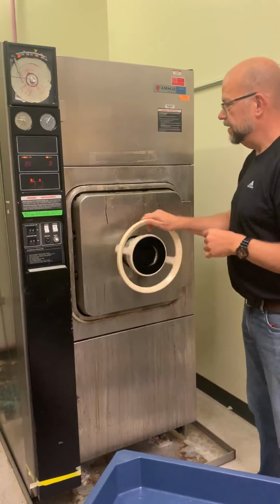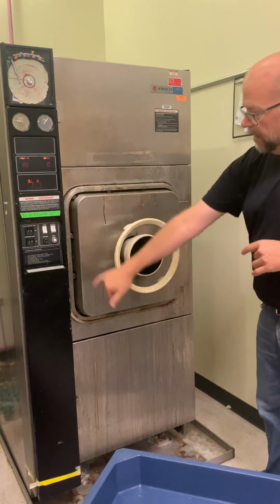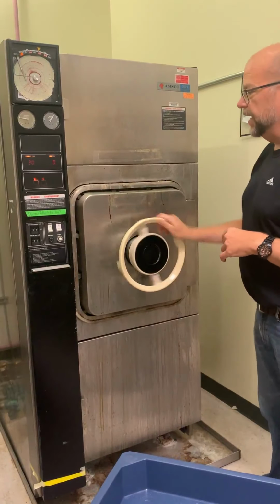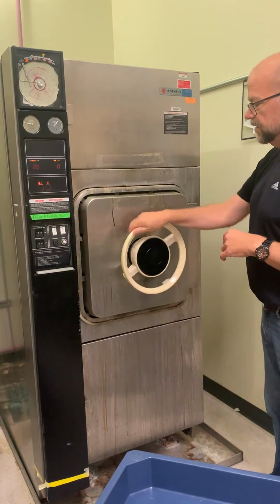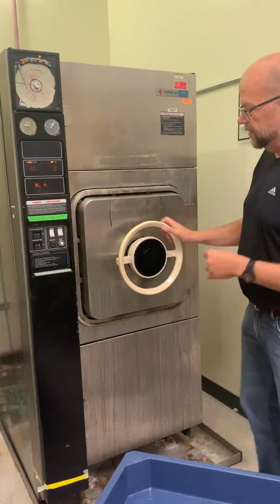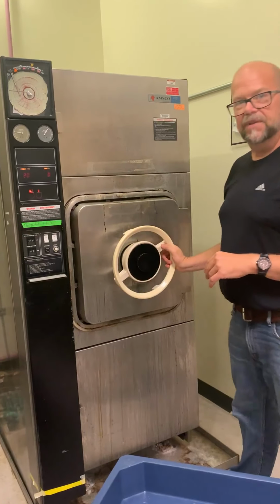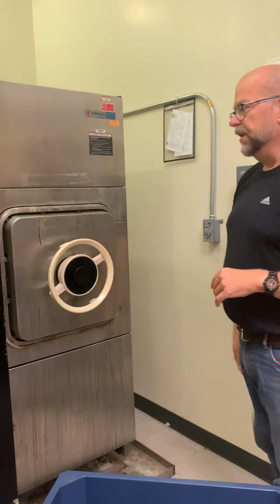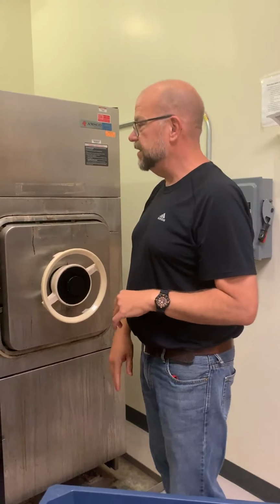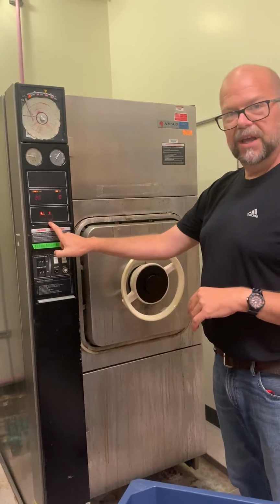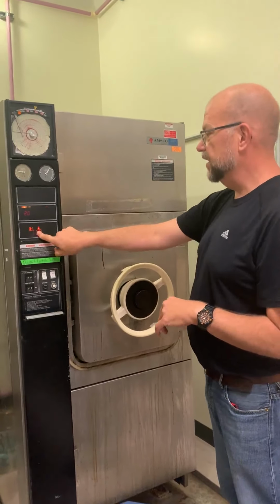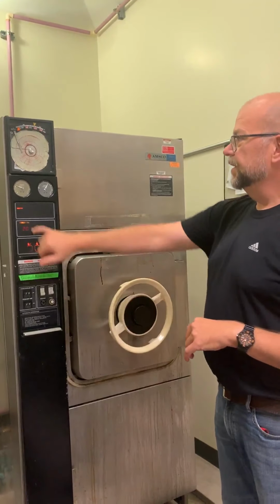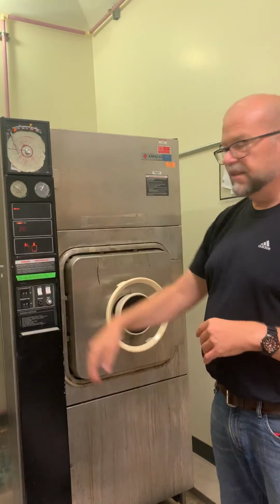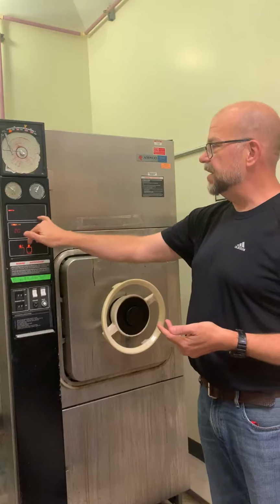We shut it. There are cleats that come up all the way around. And I just turn it until I get good resistance, and then give it another half a turn. Okay. Once I've done that, I know I've got it sealed correctly. I'm autoclaving liquid. Press the liquid cycle. The chamber is getting pressurized. And it's going to, once it gets up to condition, it's going to start to count down the time.